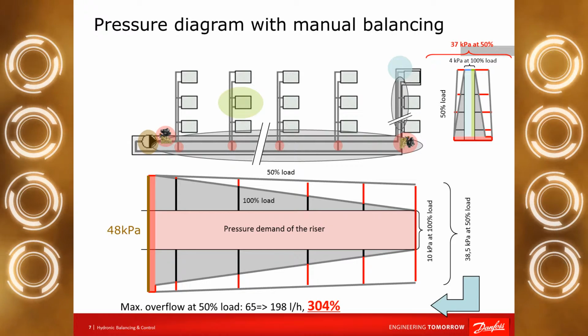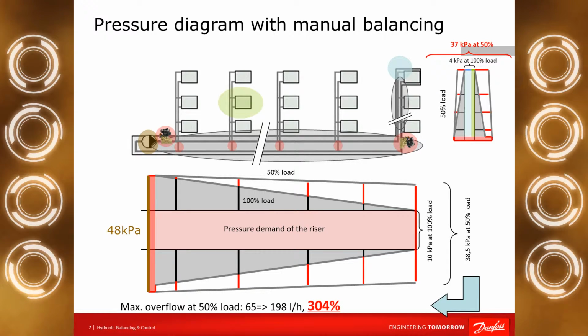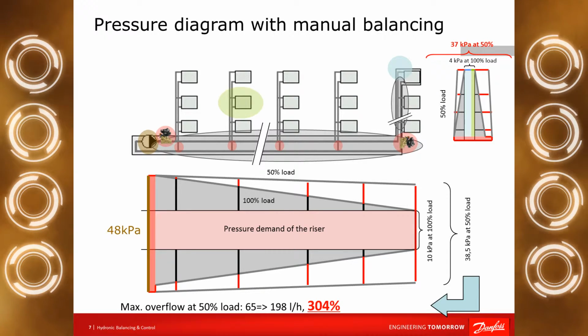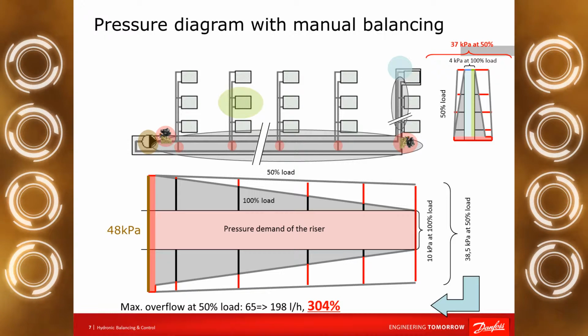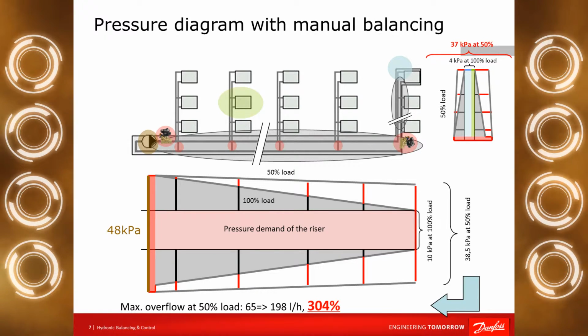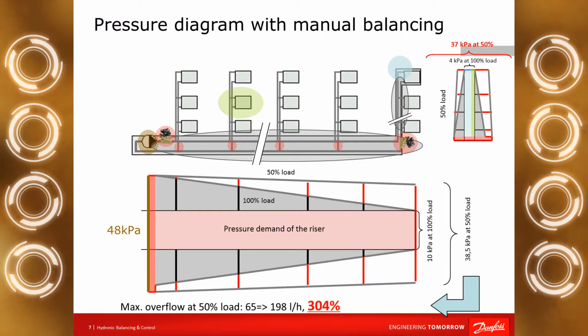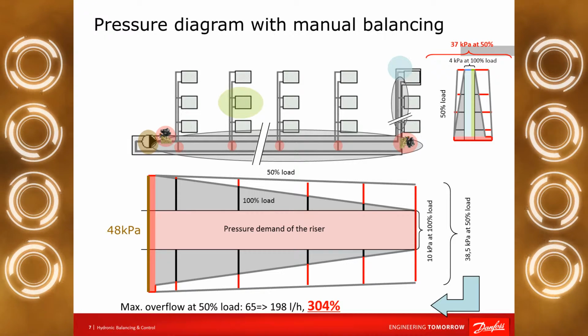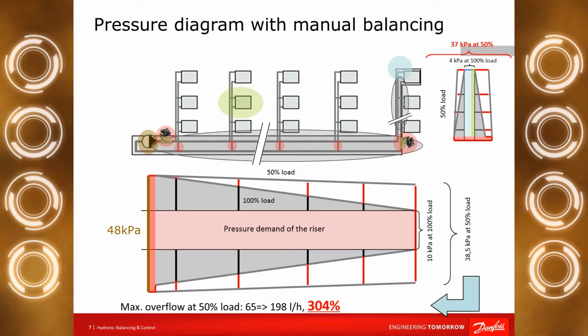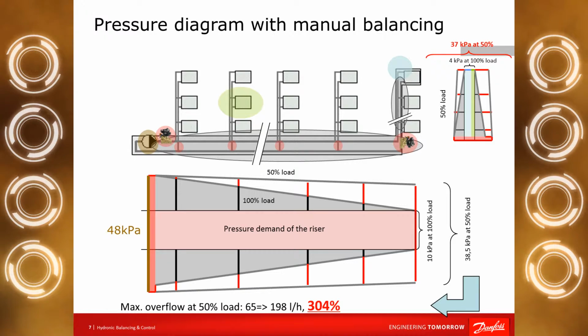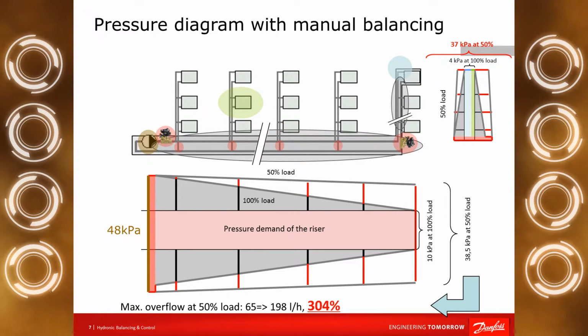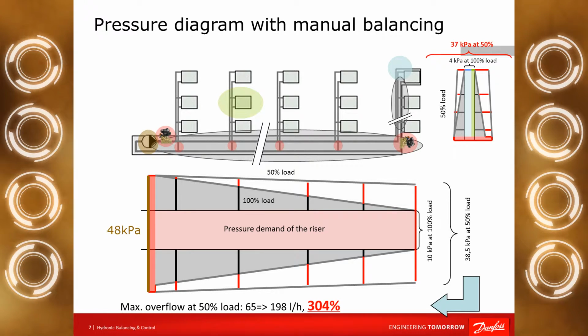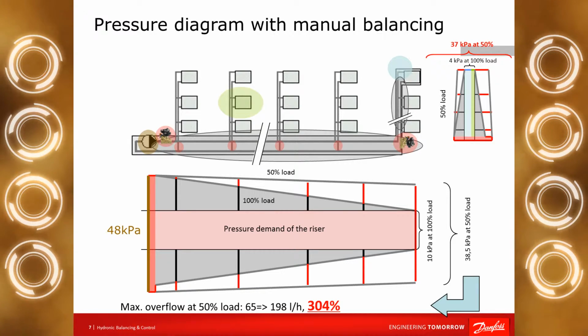No, because this is only a few hours in a year in the total season. Therefore, we have to investigate the system in partial load condition as well. Let's see what partial load condition, namely 50%. In reality, the partial load condition is even less than 50%. In reality it is 30-40%, but for easy calculation, I used this 50%.